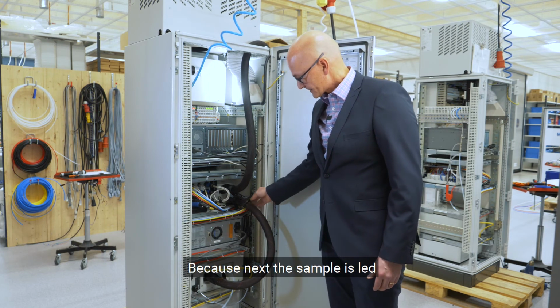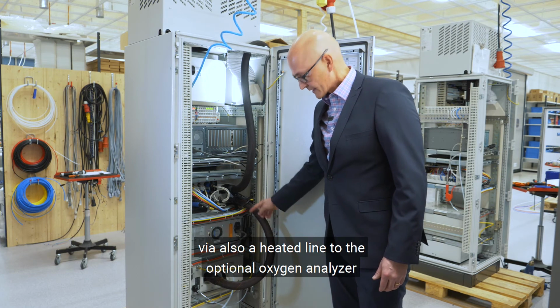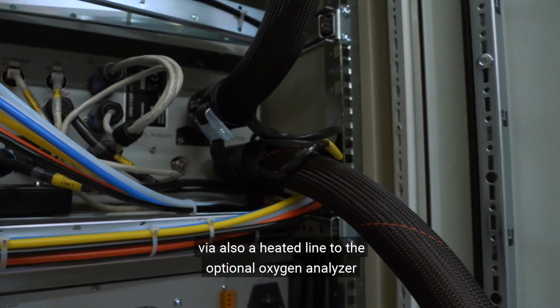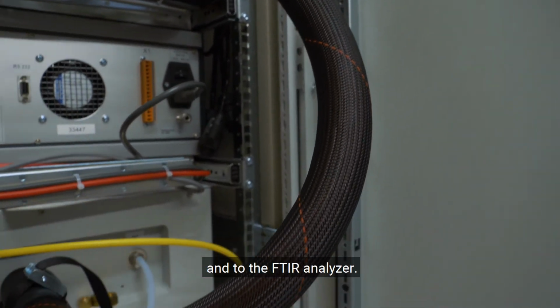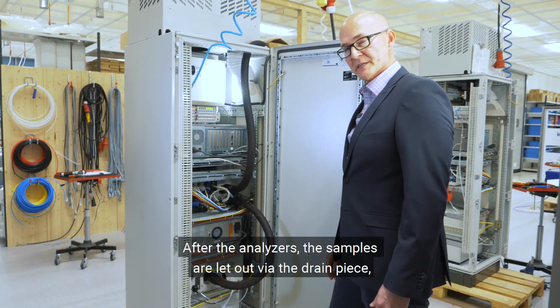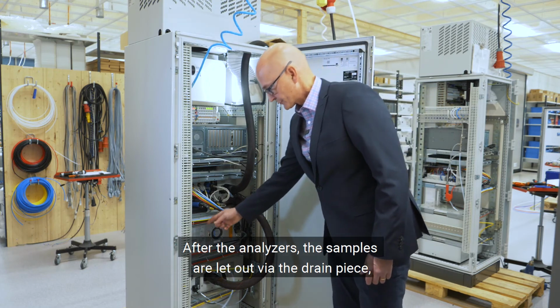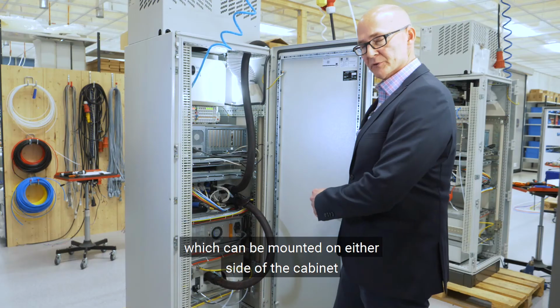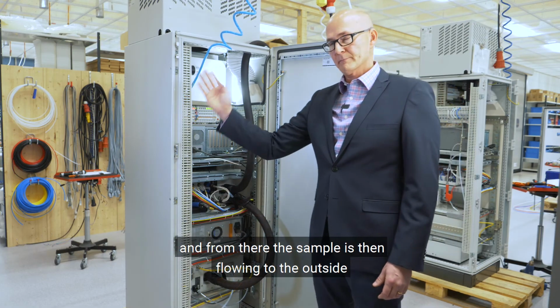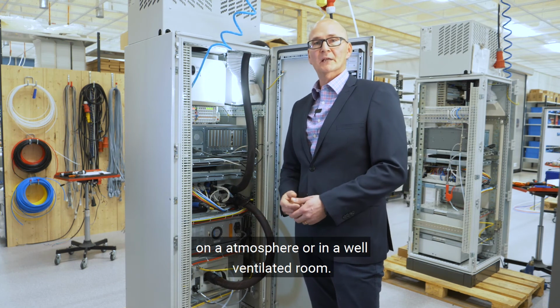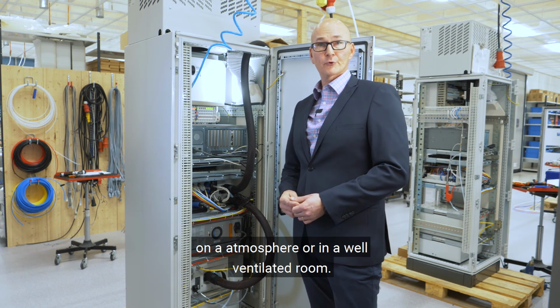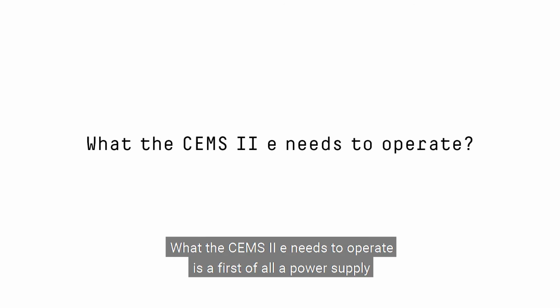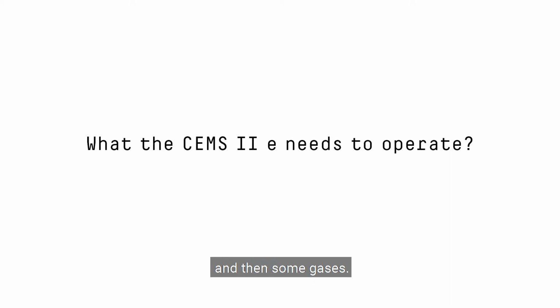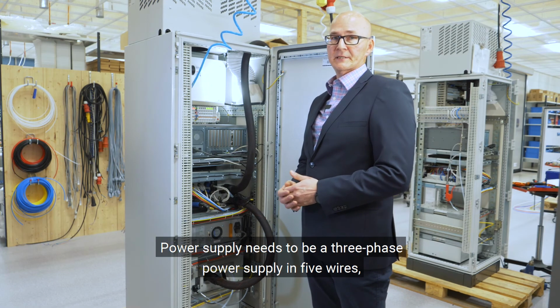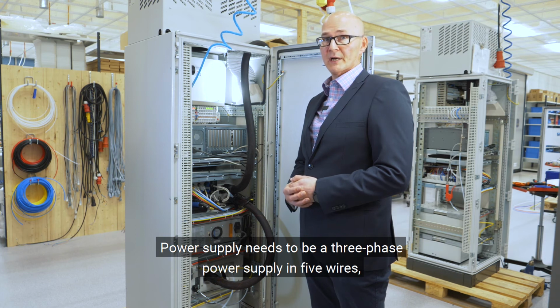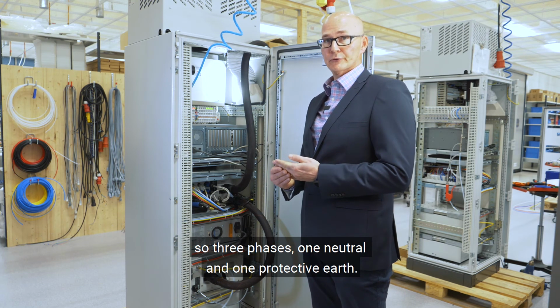Because now the sample is led via also a heated line to the optional oxygen analyzer and to the FTIR analyzer. After the analyzers, the samples are let out via the drain piece, which can be mounted on either side of the cabinet. And from there, the sample is then flowing to the outside normal atmosphere or in a well-ventilated room. What the CEMS needs to operate is, first of all, a power supply and then some gases. Power supply needs to be a three-phase power supply in 5 wires. So 3 phases, 1 neutral and 1 protective earth.